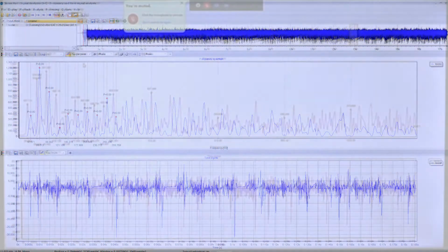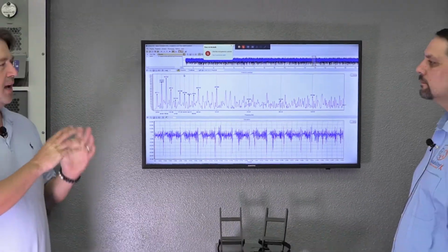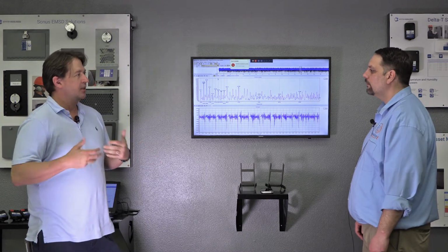If we actually drop a marker, we come up to this little highlighter, and I can mark them individually, which has been proven to be useful, or I can choose harmonics, where as soon as I put it down at that value, it's going to repeat at that value 10 times. One of the things I've noticed is sometimes with electrical faults, they might not start right at 60. So having a harmonic cursor that repeats that first value 10 times doesn't always work.